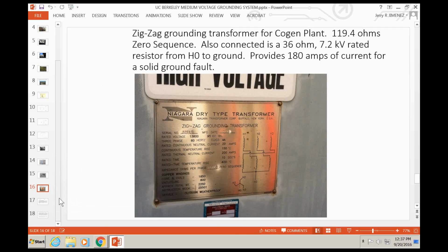And the reason is that the arcing in the vicinity of where the fault occurs often destroys nearby insulation. We get that nice controlled level of 1,000 amps of ground fault current, but as soon as the ionization happens, or maybe some arcing and sputtering that burns some insulation nearby, then we get our phase-to-phase fault. And then the ground fault more or less goes away. Those two phases, once they get connected, just start pumping current to each other, and the ground system is kind of out of it.